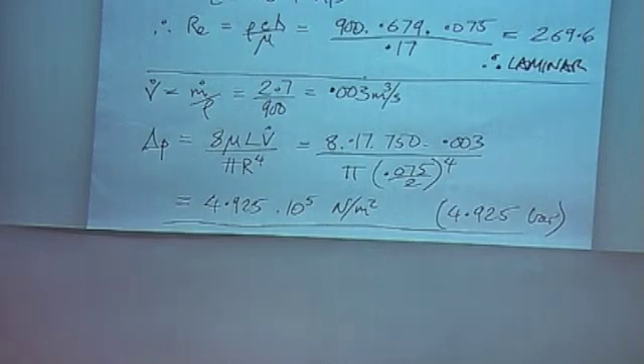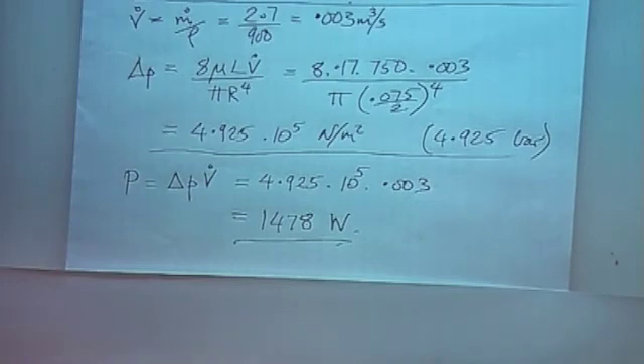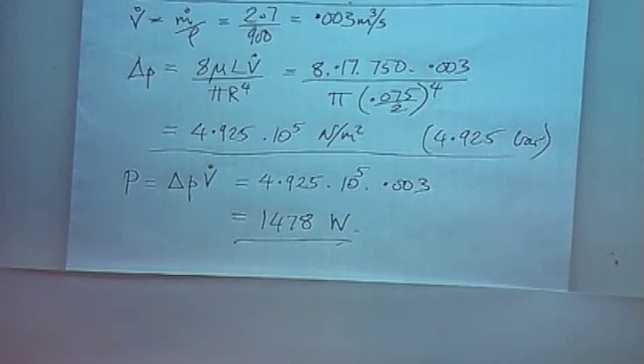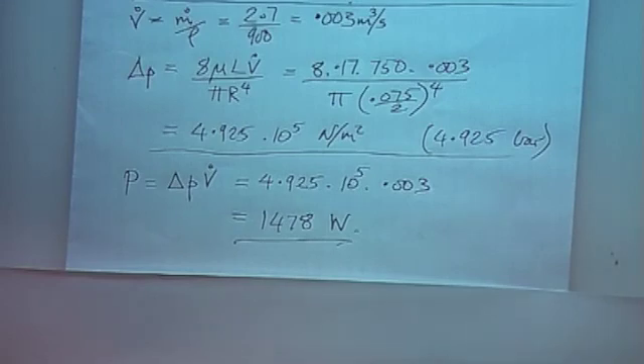Cutting to the chase, the pressure drop predicted by this formula is 4.925 bar. From which, plugging the pressure drop and the volume flow rate into the power equation, the bottom line is 1.48 kilowatts — or 1478 watts — are required to sustain this flow rate of fluid under the given conditions.